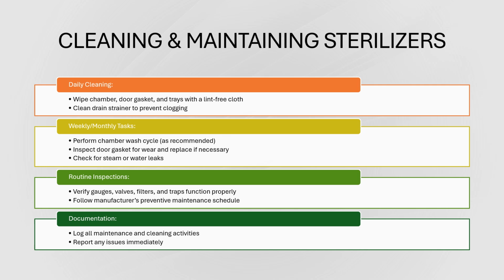Make sure you just wipe everything down with the lint-free cloth. The drain strainer, you need to clean that out to make sure there's nothing stuck in that drain, in that strainer, because if you use stamps, that stamp could come off. So sometimes it does happen. Locks come off and fall into that strainer. Me personally, every time I'm on the autoclaves, that's the first thing I check before I run a load. The book says it's every day. I like to say every shift, because you don't know if the person before you did that beforehand.